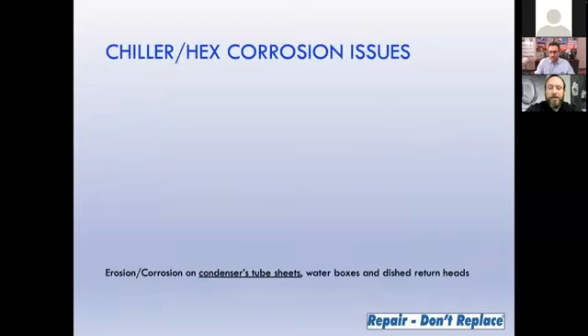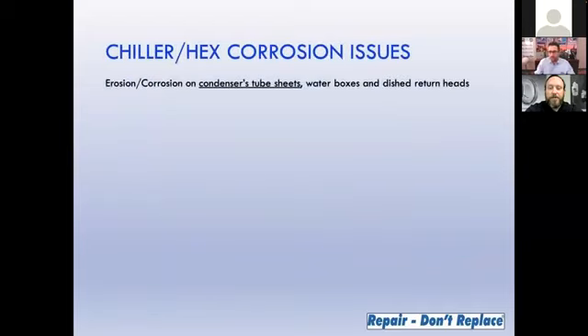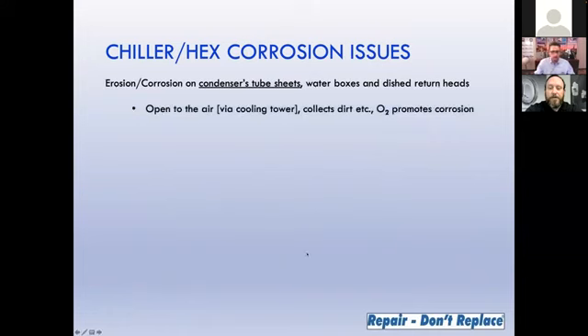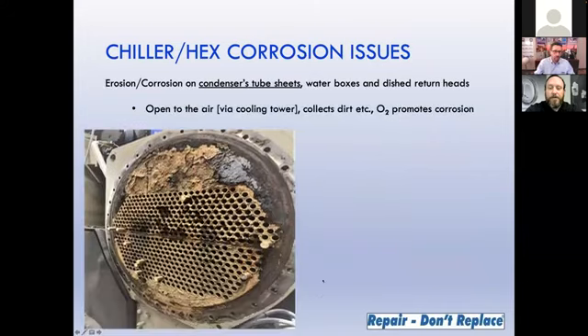The condenser of a chiller is usually where most of the corrosion issues present themselves. Being part of the open air system with the cooling tower, the unit collects a lot of dirt, mineral scale, debris, and a large amount of oxygen, which promotes the corrosion that we typically see when we come on sites for inspections. A large amount of mineral scale buildup on the tube sheet, with corrosion starting to form underneath the mineral scale.